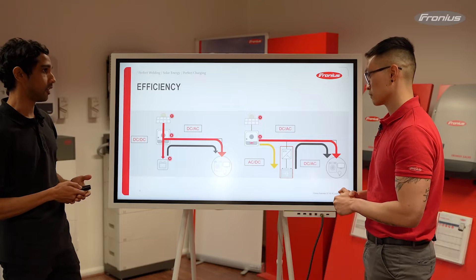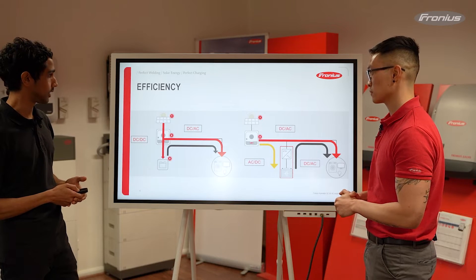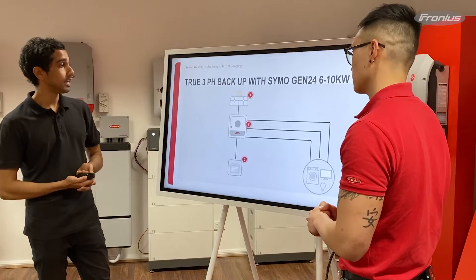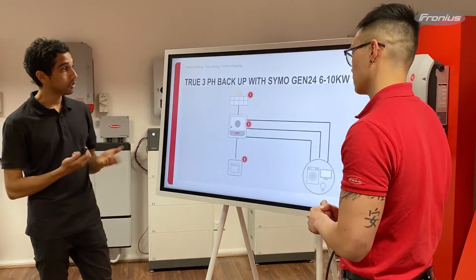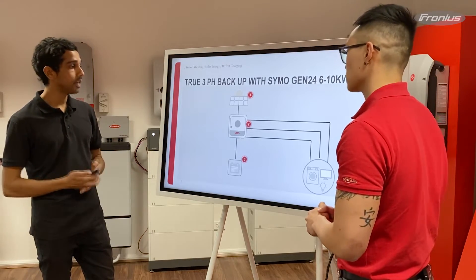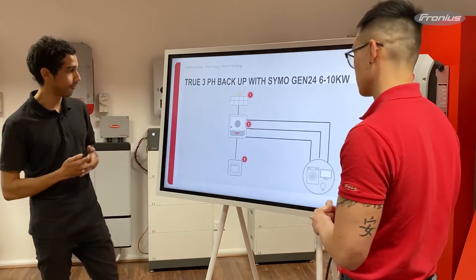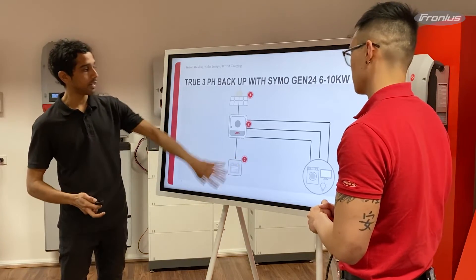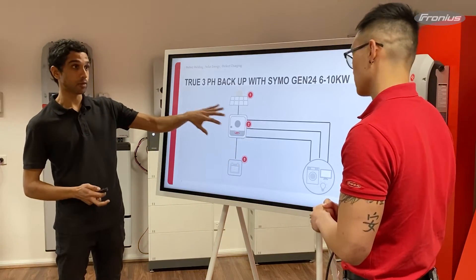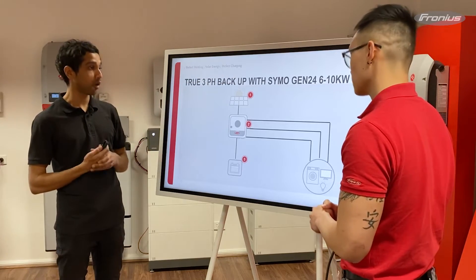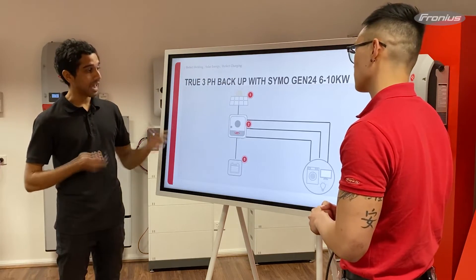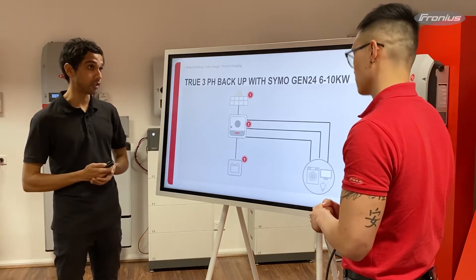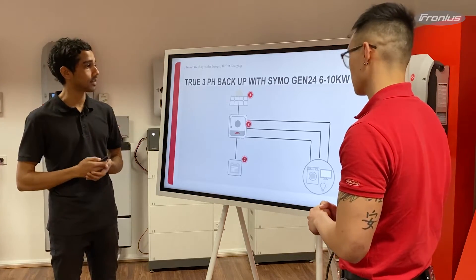So you can see the DC coupled system is a more efficient type of system. Another benefit is that you're able to do true three-phase backup, depending on the battery and inverter. For example, with a DC coupled battery attached to the Fronius Symo Gen24 in the 6 to 10 kilowatt range, you're able to do true three-phase backup of three-phase loads.